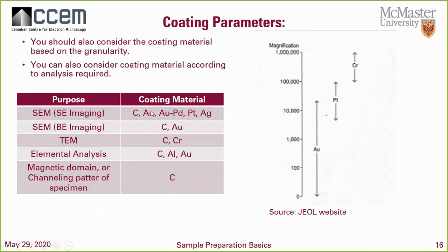Coating with carbon, gold, gold-platinum, right? If you want to do some SEM imaging, you should consider coating with these just because they're so small, and for more general use. We're not going into very high magnifications usually in SEM, so you can consider gold up to about 30,000 times, right?